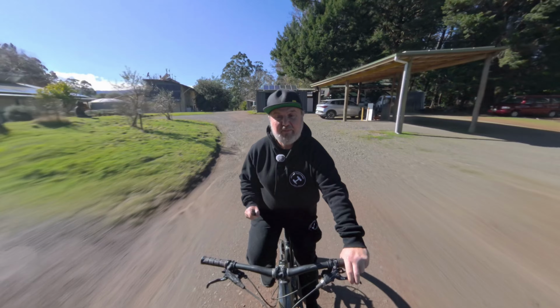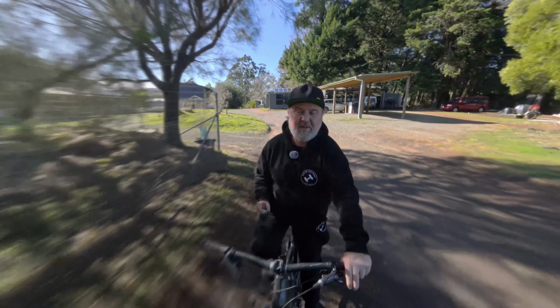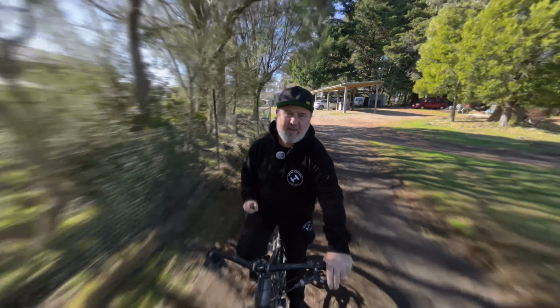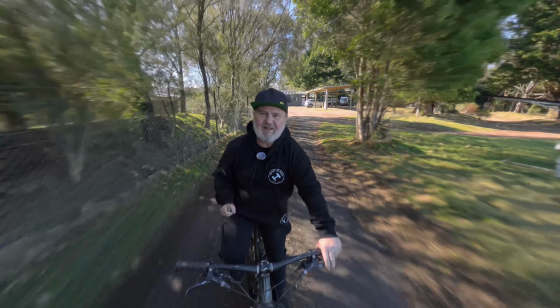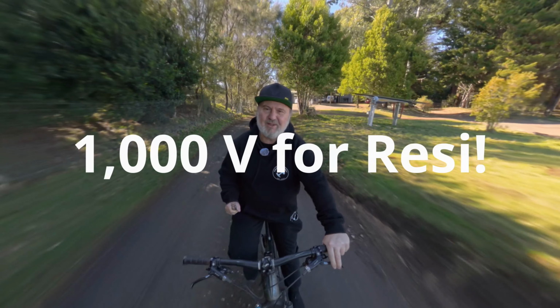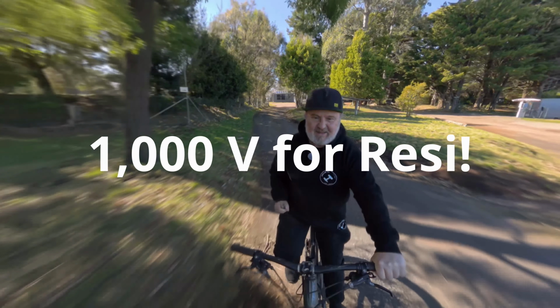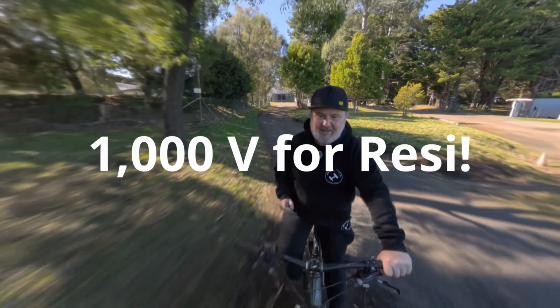If you're wondering what's changed with 4777 Part 1 2024 edition, well, quite a lot, but not the world has changed. There's been some improvements, and the big headline number is we can finally go to 1000 volts on domestic systems. Yep, 1000 volts on domestic systems. 5033 permitted it, but the old 4777 didn't.